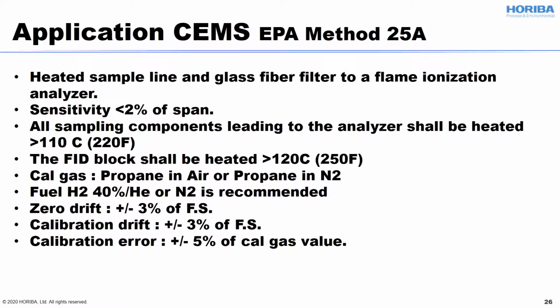All sampling components leading to the analyzer shall be heated above 110 degrees C, which is 220 degrees F. The FID block shall be heated above 120 degrees C, which is 250 degrees F. Cal gas should be propane in air or propane in nitrogen. The fuel is hydrogen 40% and 60% helium base or nitrogen is recommended. Drift is within plus or minus 3%, calibration drift is plus or minus 3% of full scale, and the calibration error is plus or minus 5% of the calibration gas value.